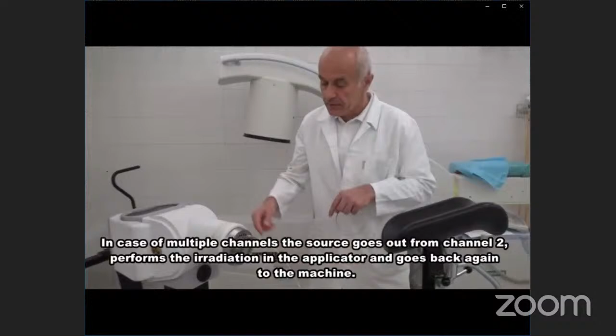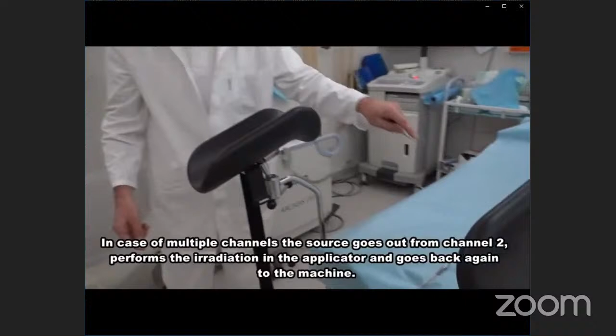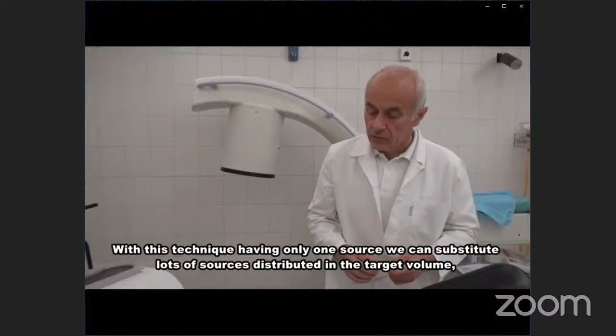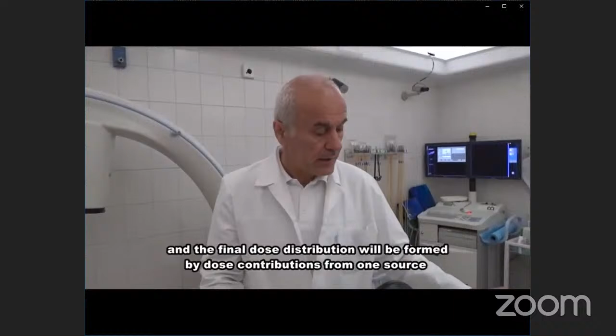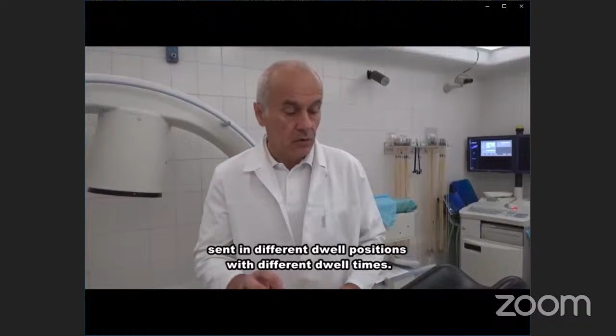So the source first goes out from channel 1, then performs the steps in the applicator and goes back to the machine. In case of multiple channels, the source goes out from channel 2, performs the irradiation, and so on. This procedure continues as many times as channels we have. With this technique, having only one source, we can substitute lots of sources distributed in the target volume. And the final dose distribution will be formed by dose contribution from one source, sent in different dwell positions with different dwell times.